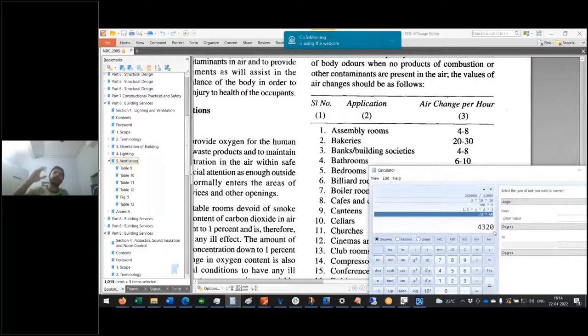So your exhaust and supply, whatever the amount of openings, your fans should be able to displace 4320. You can do it from 4 openings, 2 openings, 10 openings, doesn't matter. But at the end of the day, 4320 should be catered. Then we have to divide this by the selected fan CMH, the available CMH, and then we will get the number of fans. Exactly. Okay, so that number will be a combination of exhaust and fresh air, right?